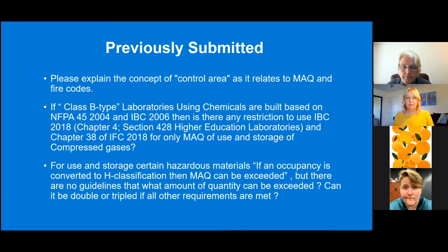When I was in graduate school, we wouldn't think anything about drilling a hole through the wall and running a cord through so we could connect our instrument over there to the computer over here. But that makes a difference if the wall you just drilled a hole through is a 1-hour firewall, and you're counting on that to segregate the hazards between the two parts of the building. So in essence, a control area is simply a collection of rooms, and in reality, you have to know a lot more about the way the building's constructed and maintained. The next question is a bit more complicated.